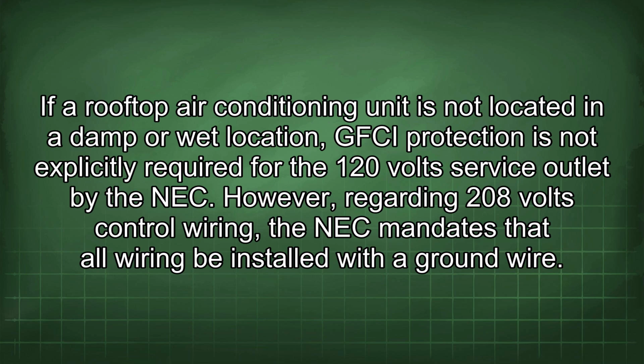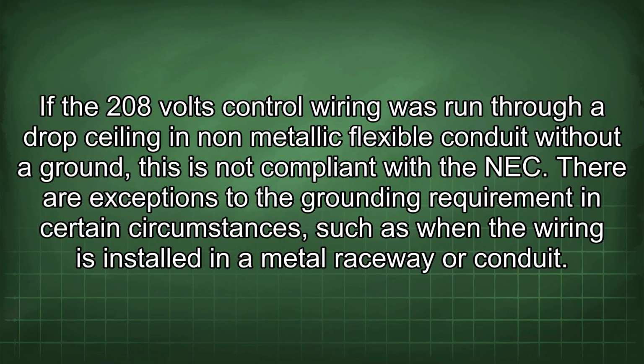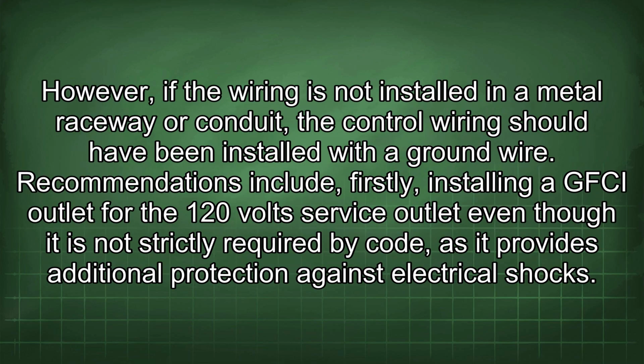However, regarding 208 volts control wiring, the NEC mandates that all wiring be installed with a ground wire. If the 208 volts control wiring was run through a drop ceiling in non-metallic flexible conduit without a ground, this is not compliant with the NEC. There are exceptions to the grounding requirement in certain circumstances, such as when the wiring is installed in a metal raceway or conduit. However, if the wiring is not installed in a metal raceway or conduit, the control wiring should have been installed with a ground wire.